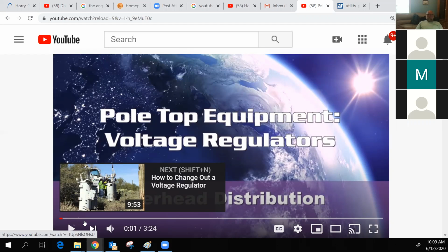It just keeps the voltage on the line within the 5%. It takes a high or low voltage and offsets the plus or minus. So if the voltage is too low, it'll maintain it at a plus value. If it's too high, it'll maintain it at a negative value. That's right, that's excellent, that's exactly what it does.